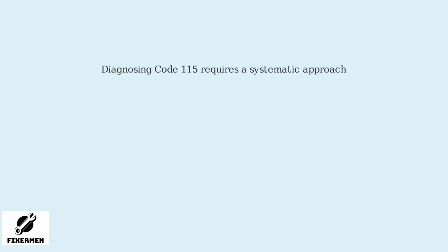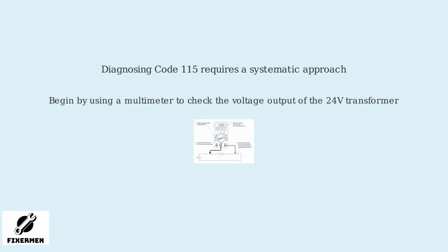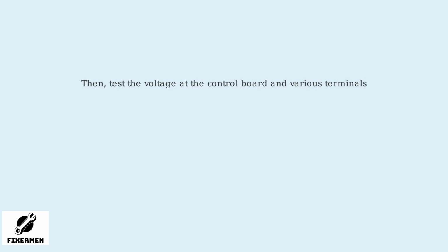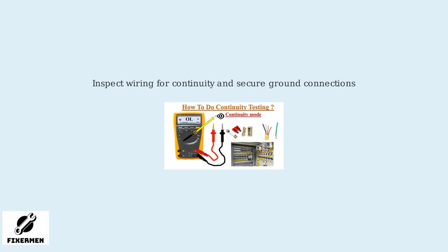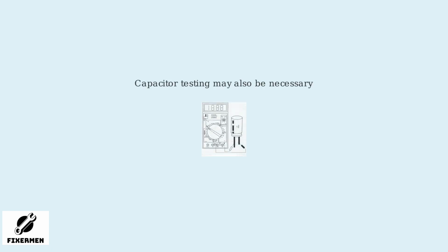Diagnosing code 115 requires a systematic approach. Begin by using a multimeter to check the voltage output of the 24 volts transformer. Then test the voltage at the control board and various terminals. Inspect wiring for continuity and secure ground connections. Capacitor testing may also be necessary. Always disconnect power before servicing to avoid electrical shock and use insulated tools.